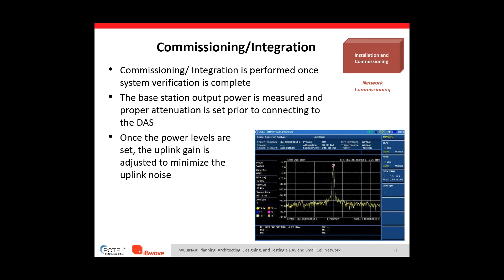So commissioning and integration is performed once the system verification is complete. System verification is that uplink and downlink testing to prove that the DAS is functioning properly. Now that we know that is done, we are ready to commission the wireless service providers and their base stations onto that DAS. So the base station output power is measured and proper attenuation is set prior to connecting to that DAS. Once those levels are set and the base stations are connected, we will do an uplink gain adjustment. And what this does is it adjusts the gains on the uplink to minimize the noise coming from the DAS into the base station, so that we look at the noise floor on the base station to ensure that we are at the lowest noise floor possible. And what this does, it allows the throughputs to perform at peak performance.